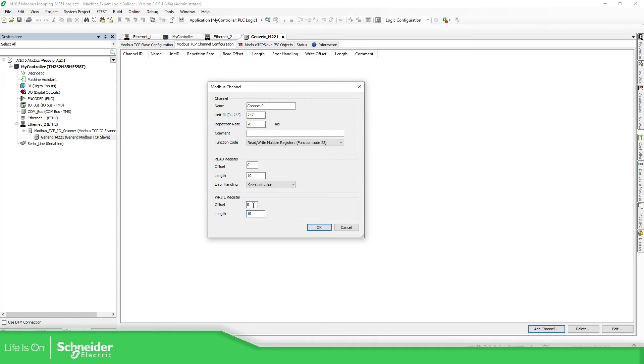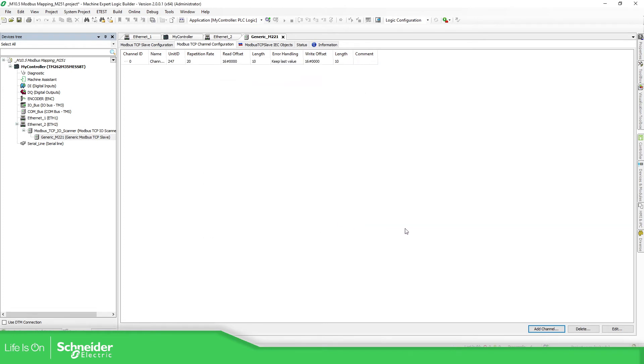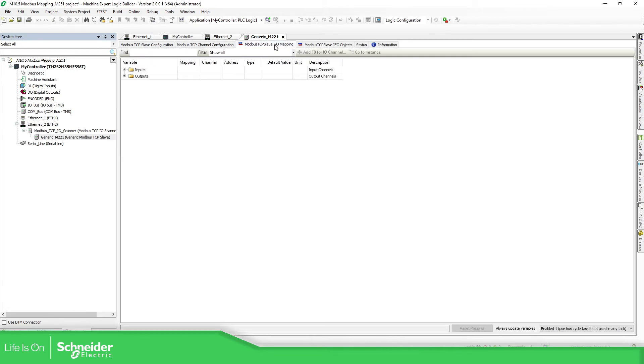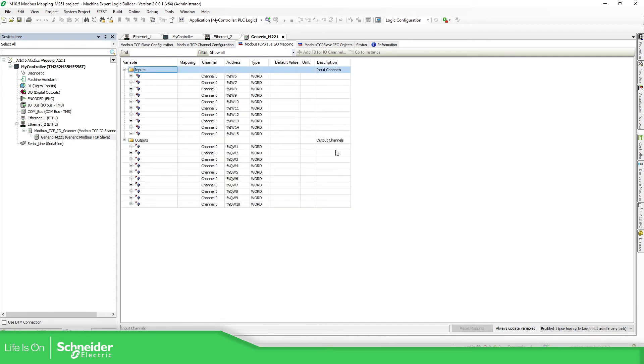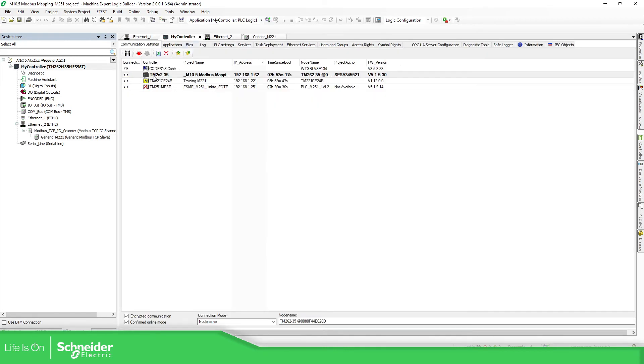The offset will be 0 and the length will be 10 — we're going to read 10 registers. This all starts from 0. You can also add some comments. The channel is now added, and if you go to the Modbus TCP slave I/O mapping view, you can see all the registers we're going to read and write from the controller.